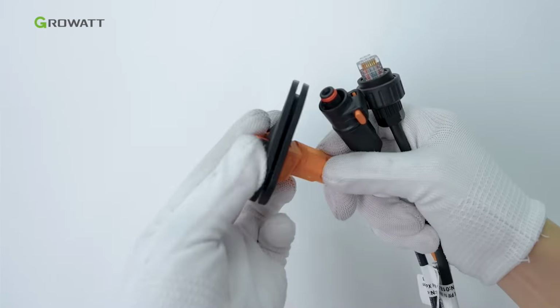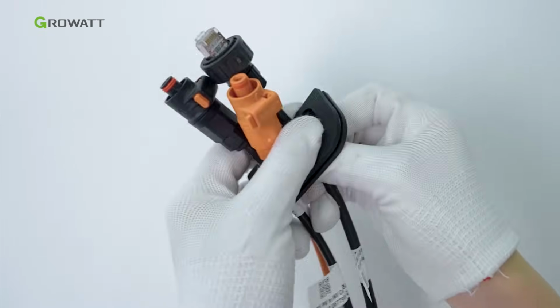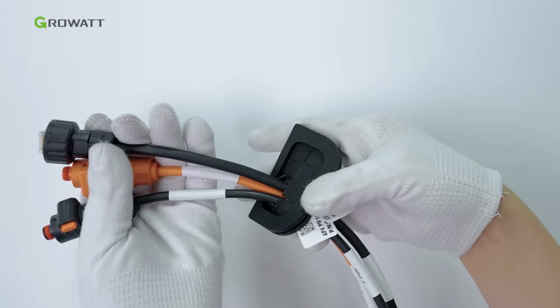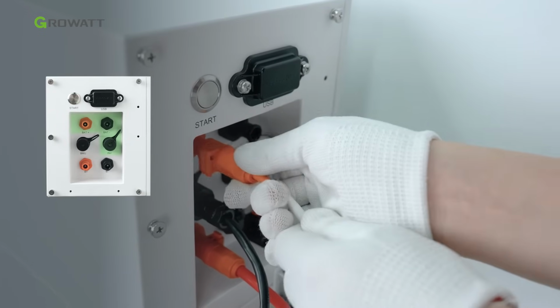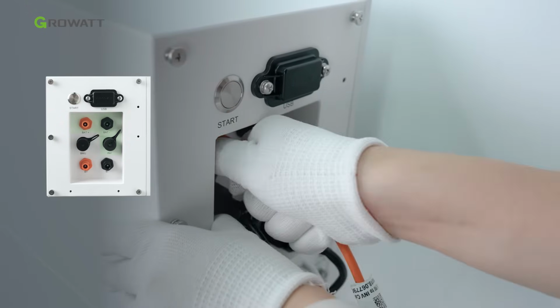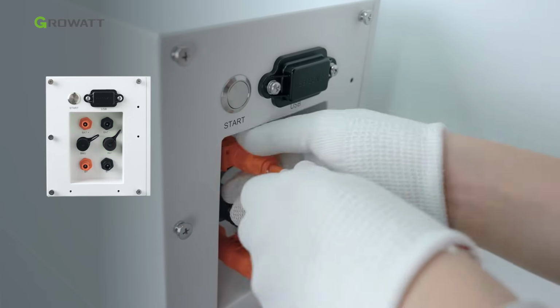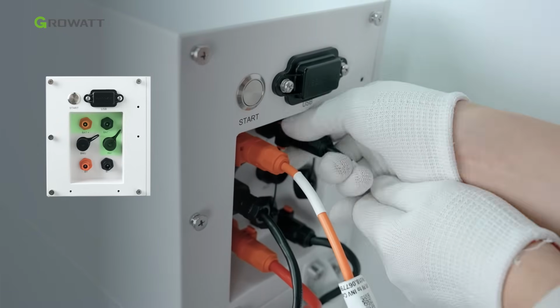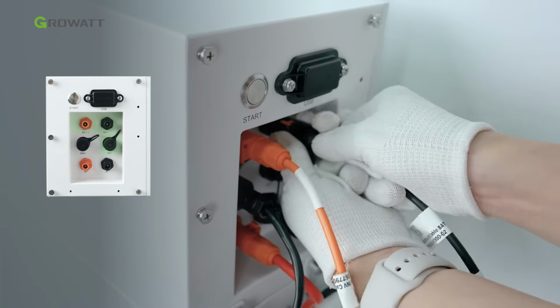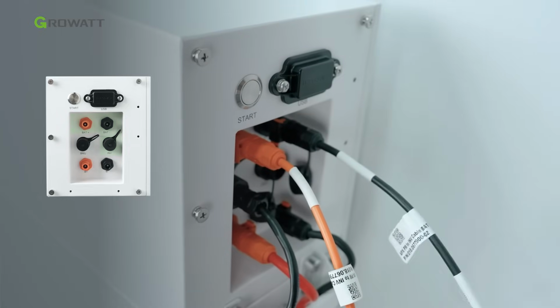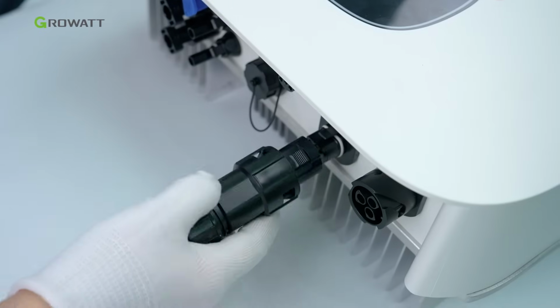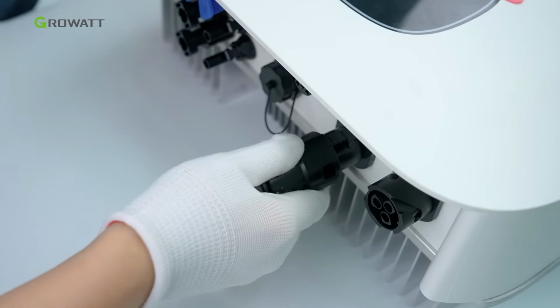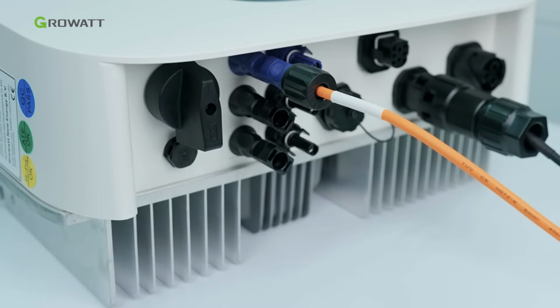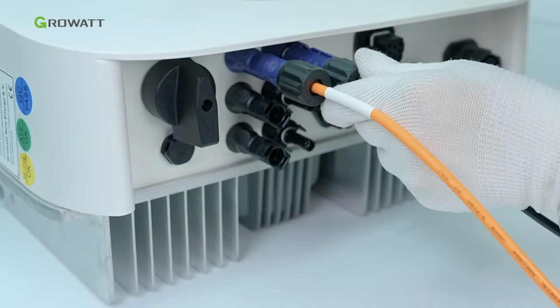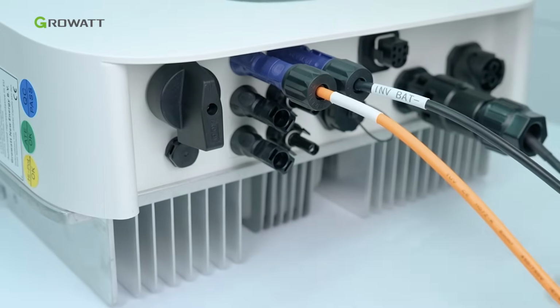Thread the power cable and communication cable from the inverter through the protective rubber ring and connect them to the corresponding interface of the P0 power module. Then attach the protective rubber ring to the side protection flap. Plug the communication connector onto the MIN XH and connect the positive and negative terminals of the battery power cable to the MIN XH.